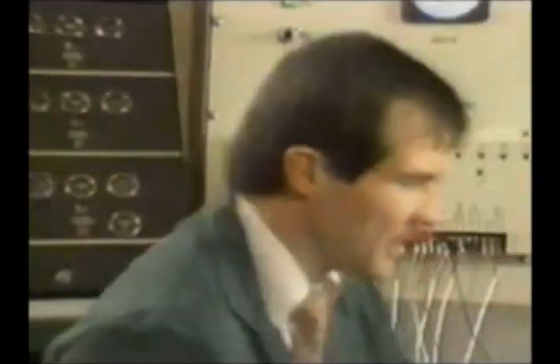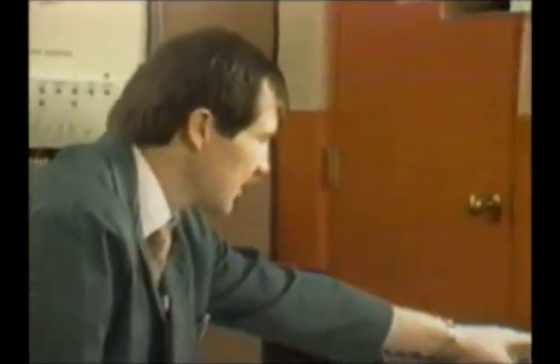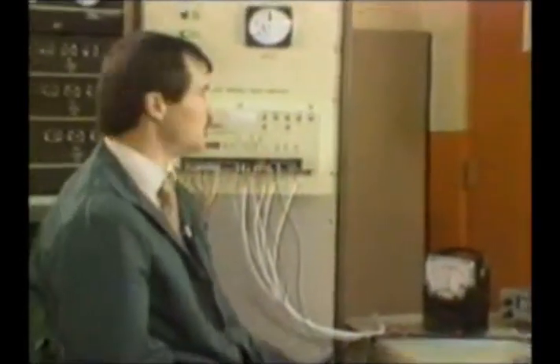Now to show you how this works, you can bump your actuator linkage and see how quickly it responds to come back to stable setting. But instead of doing that, here I have the capability of using a resistive load bank. So I can actually put load on my prime mover. I can watch my Hertz meter to see the reaction time of the Hertz meter. Now I need to close my load breaker. And now I'm going to start adding load to the prime mover.